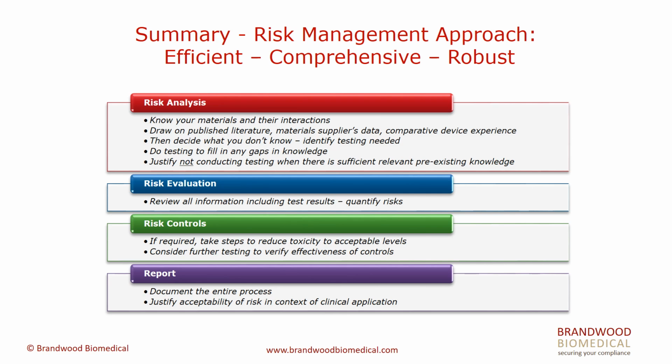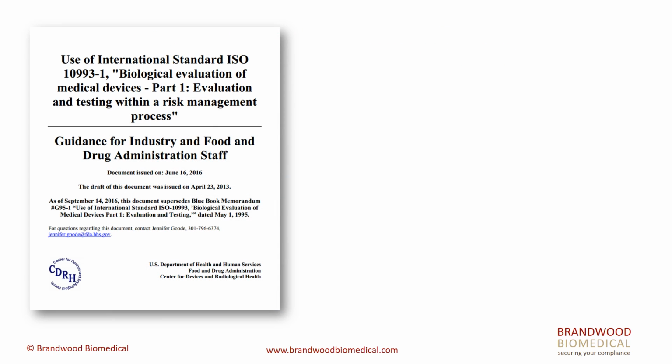Evaluate the whole thing, that's the risk evaluation step, including any test results, quantify the risks, introduce any risk controls you need to do, and then report. Now, I'd point out that this risk management approach is well understood by regulators. This guidance from the United States FDA released earlier this year certainly completely embraces the risk management model.